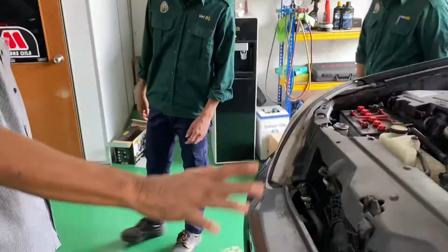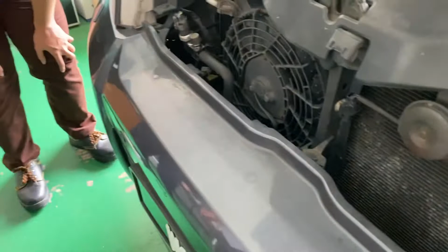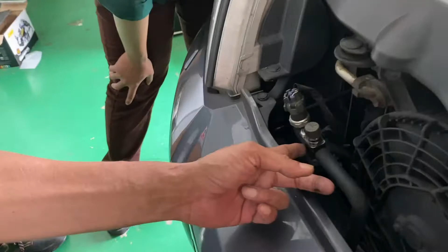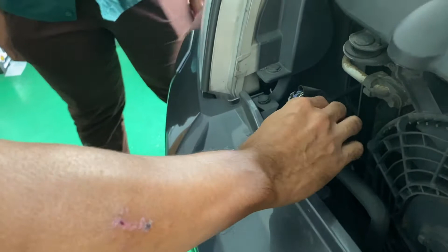You have already discovered basically the condition. Not to say very good, not to say bad. You can see the condenser is not really very good like a normal condenser, but from my observation, there's no identical leak. When you look for a leak, look at the line for any oil accumulation or dirt accumulation around the connection. That is the true observation. Just look thoroughly and understand the system.